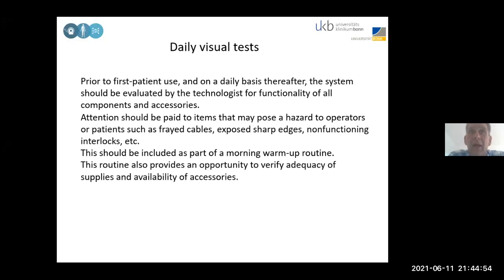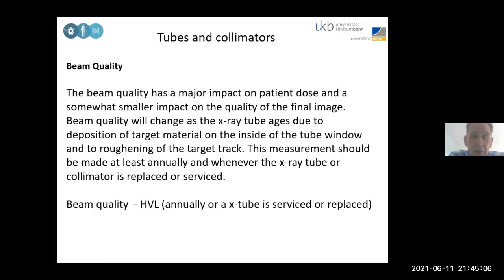Write that down and let it be signed by the person who has done it, and signed by another person who controlled what the person has done. So two signatures I recommend. Beam quality, that is also a very important parameter. At kV and the current and the voltage is one part, but the beam quality itself you can measure best with the half value layer. So that's a typical phantom, which for certain energies reduces the intensity by 50%. And if you have one of those for the certain energies you usually use, then you should try to do those checks on at least a half-year basis. Most of the protocols I know recommend annually.